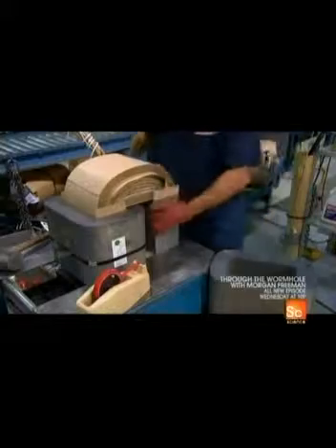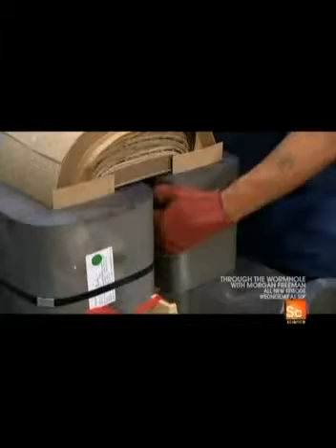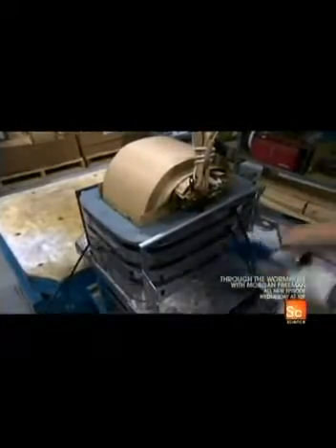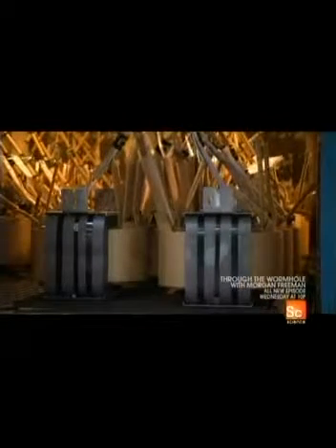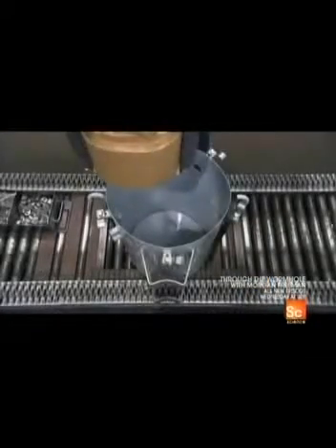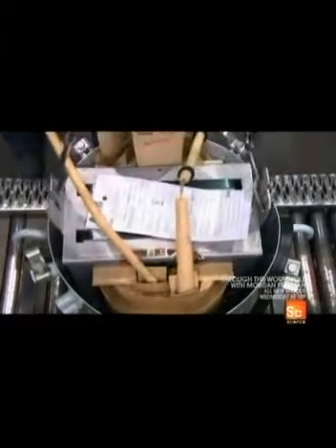This completed unit is called the coil. Using electrical steel, workers build the transformer's other main component, called the core. The coil and core are tightly secured together with metal strapping, which helps fix the assembly in the tank. Then it's into an oven where they bake for eight hours at 275 degrees. The heat improves insulation by removing any traces of humidity, and also melts the epoxy glue, fusing together the paper, the aluminum strip, and the copper wires.